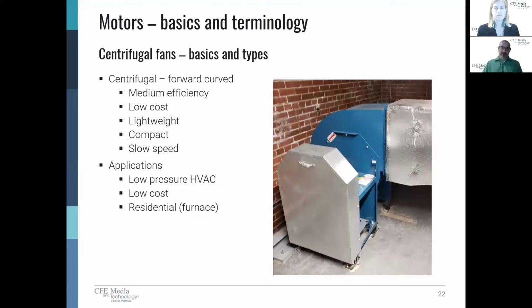What most of you are going to be very familiar with are forward curved centrifugal fans. And why is that? Because they're what's most commonly used inside furnaces. When I had to replace the forward curved centrifugal motor in my furnace, it was only $65 and it maybe took a couple hours. Not that big of a deal. Now, they're very low cost. They're fairly lightweight. They can build all the blades out of a single sheet of metal. And that's kind of what they're known for, right? You have a bunch of small, tiny little blades, 20, 30, or 40, that are pushing air.